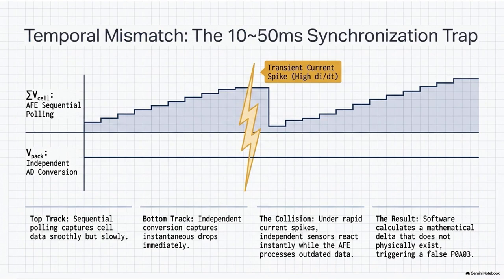You've identified the core challenge of functional safety at speed. That is why the driving phase relies on a completely separate protocol called voltage failsafe mode. How does that work? If a severe rationality mismatch is confirmed at highway speeds, the primary directive shifts from protecting the hardware to protecting the occupants. The BMS executes a logical override. It essentially declares the total voltage sensor a compromised entity and cuts it completely out of the logic loop. Wait, it actively ignores a critical safety sensor. It has to. It switches entirely to relying on the sum of the individual cell data provided by the LMUs to maintain basic operational awareness.